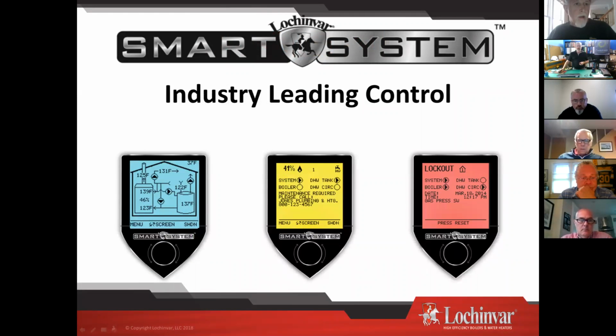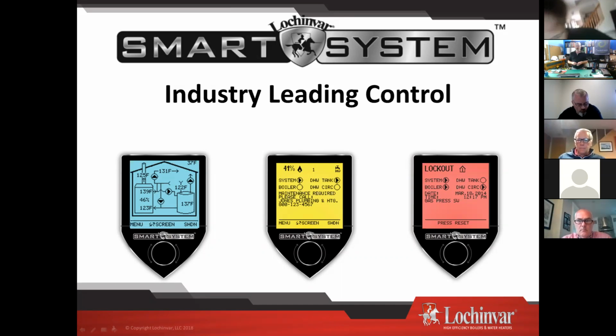So a couple of different colors that go on within the screen as to what we're looking at and what we see. When we look at that screen, there's three colors to the screen now. There's the blue screen, that's normal operation. Now that blue backlighting generally only stays lit for 2 to 3 minutes. That is adjustable in the control parameters if you want to make it longer. But when you touch it, the backlighting is going to come on. It's that blue backlighting. Now, the yellow screen, that's maintenance required. That's like a change of oil light coming on in your car. That's really all that is, really nothing more than that.